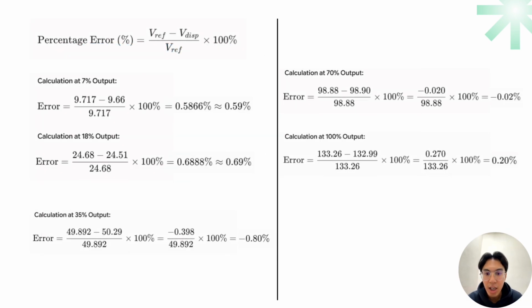To understand exactly how those error margins were determined, let's look at the mathematical verification on this slide. We utilize the standard percentage error formula, which is the absolute difference between the reference voltage and the display voltage, divided by the reference voltage and multiplied by 100 to get the percentage. On the left side of the slide, you can see the step-by-step calculation for the lower operational range. For example, at 35% output, the formula processes a reference of 49.892 kilovolt and a display value of 50.29 kilovolt.